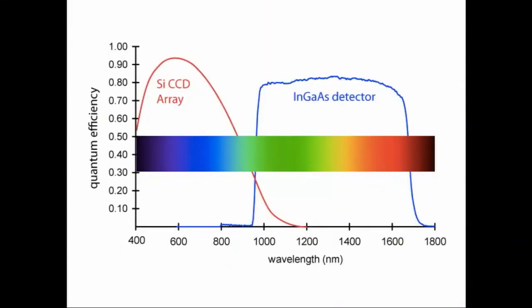The next thing we need to think about, regardless of the construction of the instrument, is the type of detector that it uses. You might say this is getting a little deep for a practical presentation, but it is important to know that there are two main types of detectors out there, and they really change the utility of the instrument to capture spectrum in the NIRS range. There are two types, the silicon-based and the InGaAs-based, and the InGaAs stands for the types of materials that are used to create the semiconductor.